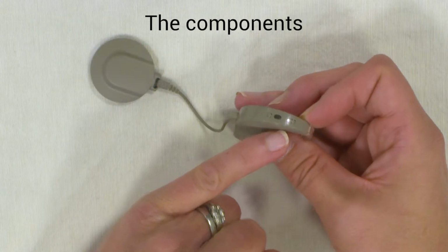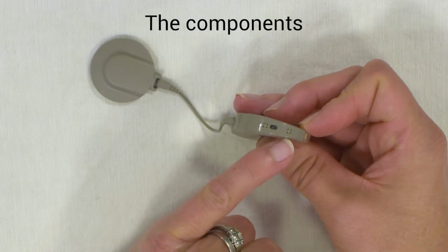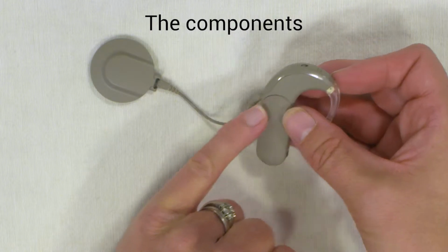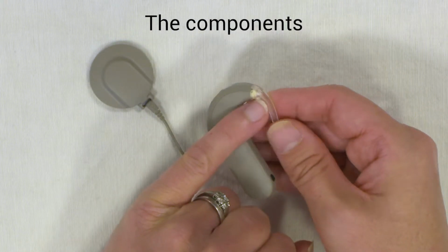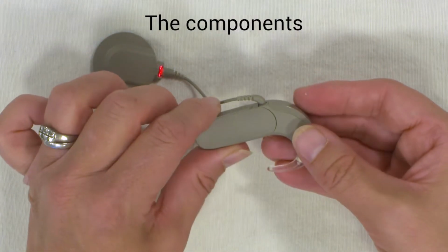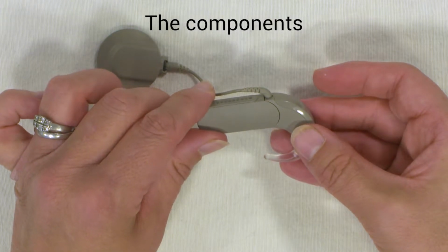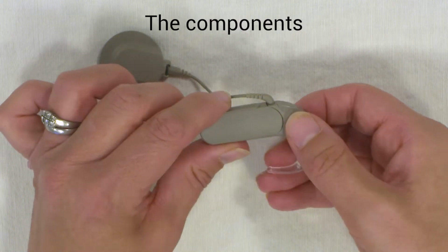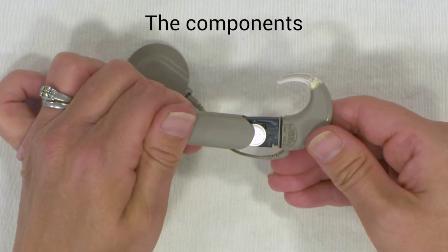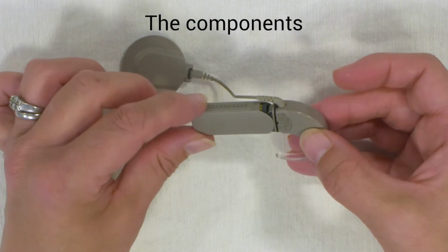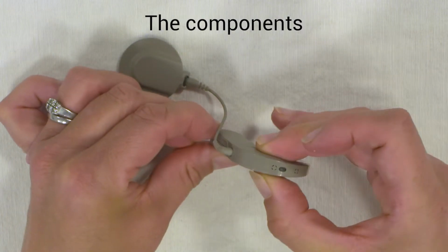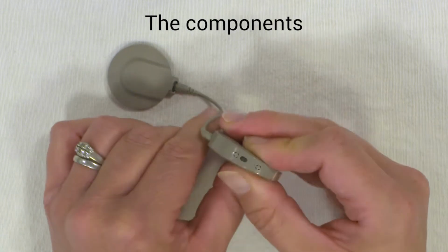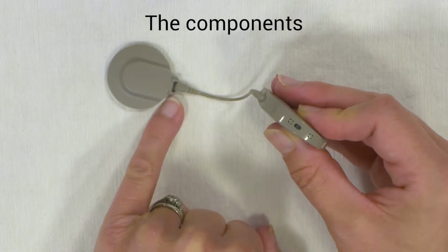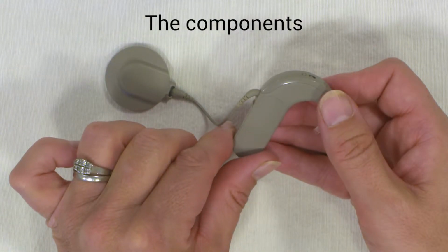This is the processor unit itself. It's got microphones at the top here that are picking up the sound, converting it into an electrical signal and then passing it along to the coil across to the implant. The processor has an ear hook and the battery which connects onto the base of the processor. To switch the processor on and off, you slide off the cover and that turns the processor off, and to turn it back on again, you slide it on. Make sure it clicks all the way on, and then you'll get a light at the top and the light here to say that the processor's working. Sliding it off again will turn it off.